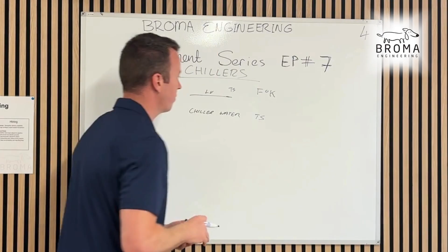So room ready, is the chiller going to a room? Room ready is quality, that's the quality manager, QA/QC usually called. Is the room ready to take the equipment? On top of that, you need a roll-in route. If it is in a room, it usually isn't, but there needs to be some sort of quality control wherever that chiller is going, that it's ready to take the chiller. If it's steel, it might be as simple as the holes are drilled, there's no swarf, no debris, nothing up there that can be blown in the wind and smash against it. It's clear, ready to go.